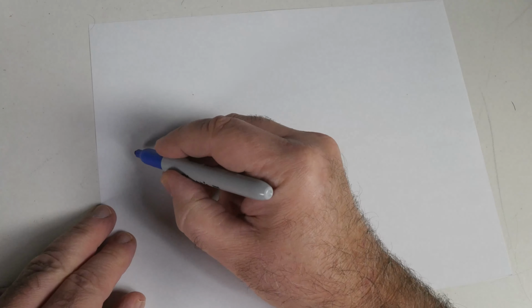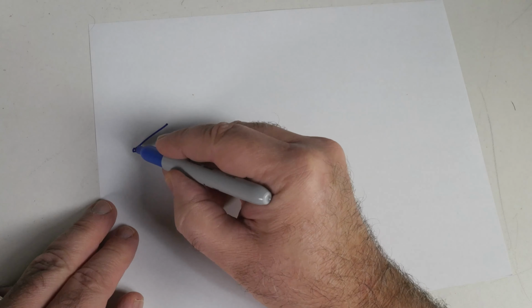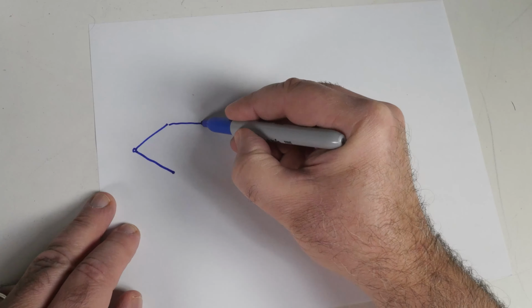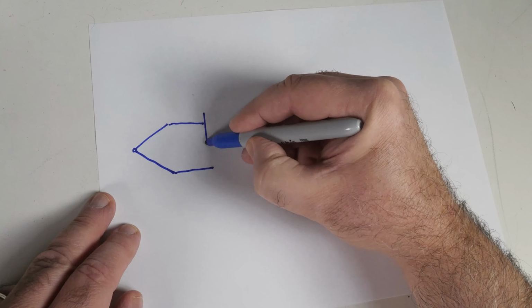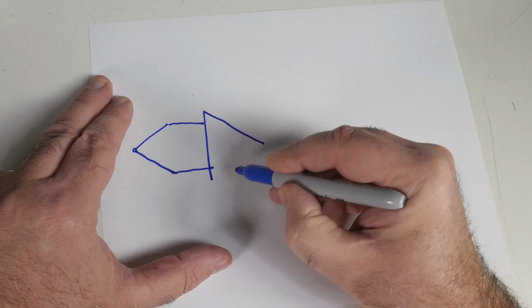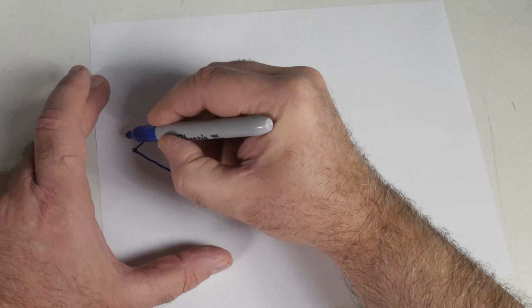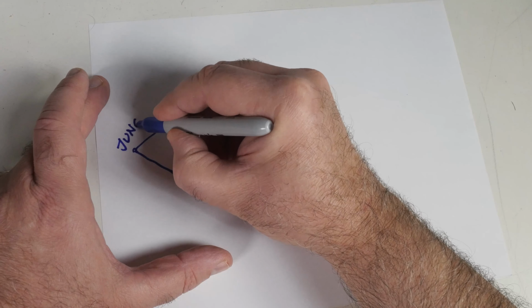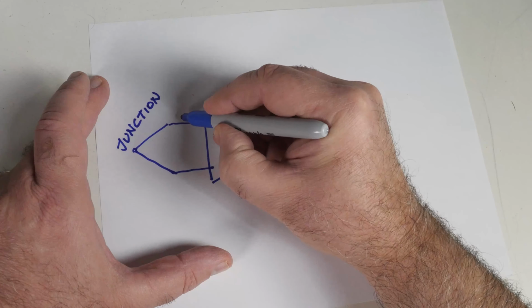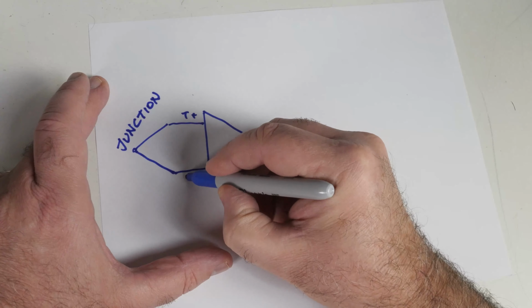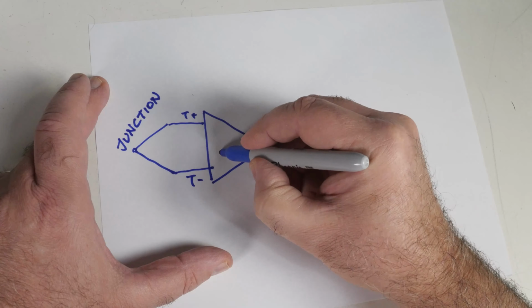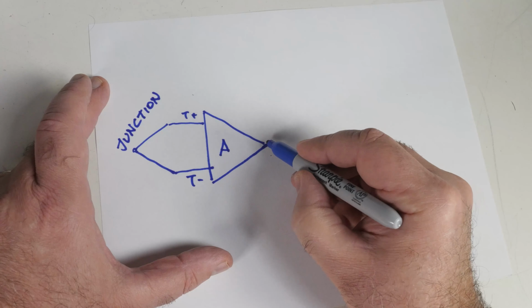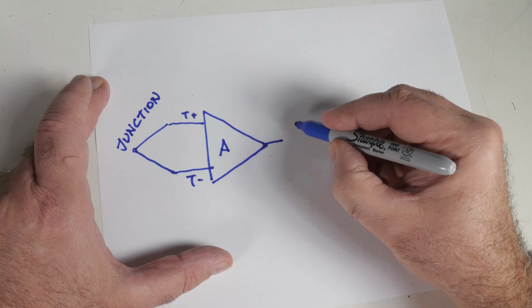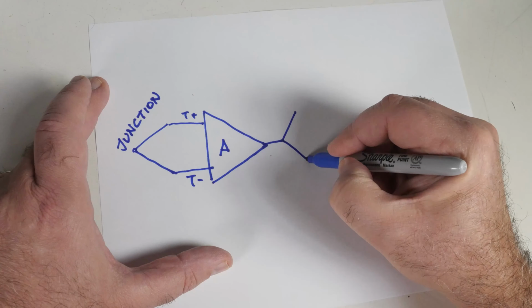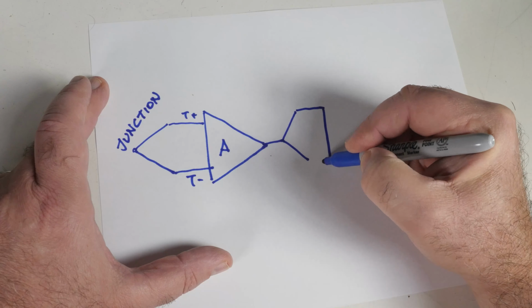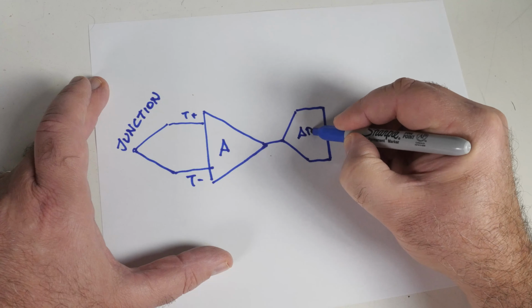To use a thermocouple with a microcontroller, we first need an analog front-end amplifier to increase the voltage range from the thermocouple from millivolt levels to the input range of the microcontroller's ADC. So a 0 to 100 millivolt voltage range generated by a thermocouple must be amplified to the 0 to 3.3 volts or 0 to 5 volts input range of a microcontroller ADC. Next, we need a high-resolution A to D converter. Microcontrollers typically have 10 to 12-bit ADCs. Given the wide range of temperatures, this is not sufficient. An ADC of 20 or so bits is needed.